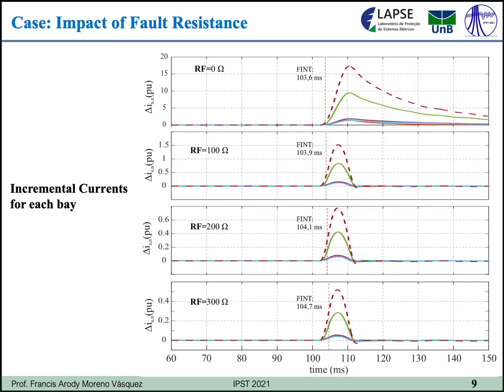Now the proposed method is tested for different values of fault resistance, and we can observe that the operation time is higher as the resistance is higher. Here we simulate faults from 0 to 300 ohms, and we can see that the difference between the best case without fault resistance and the worst case with 300 ohms is only approximately 1 millisecond. So it means that the algorithm provides a good response for these scenarios, even in the presence of a high resistance fault.